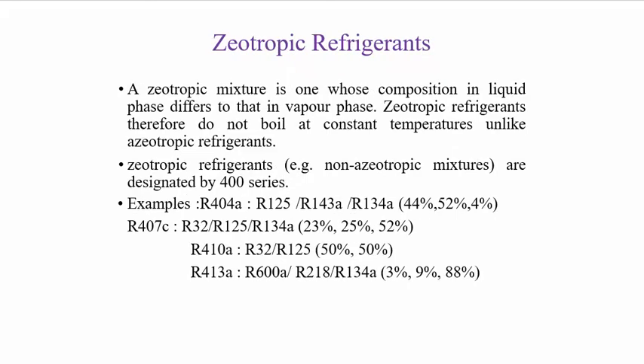Then we have zeotropic refrigerants. A zeotropic mixture is one whose composition in liquid phase is different from that in the vapor phase. Zeotropic refrigerants therefore do not boil at constant temperature. Unlike azeotropic refrigerants, zeotropic refrigerants are designated by the 400 series. Examples are 404A, 407C, and many more.